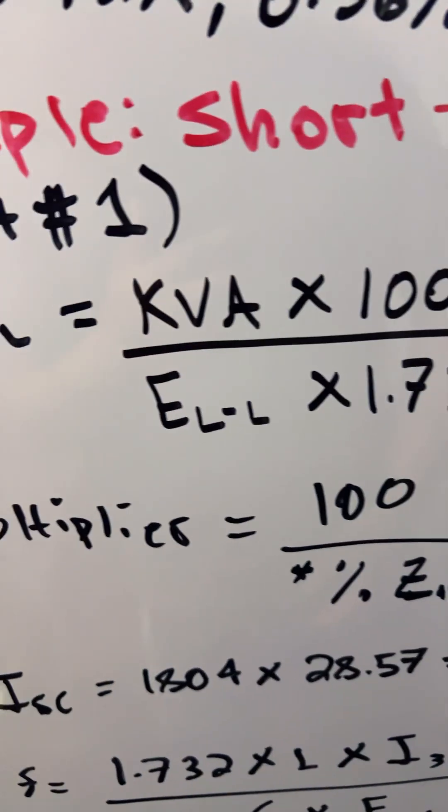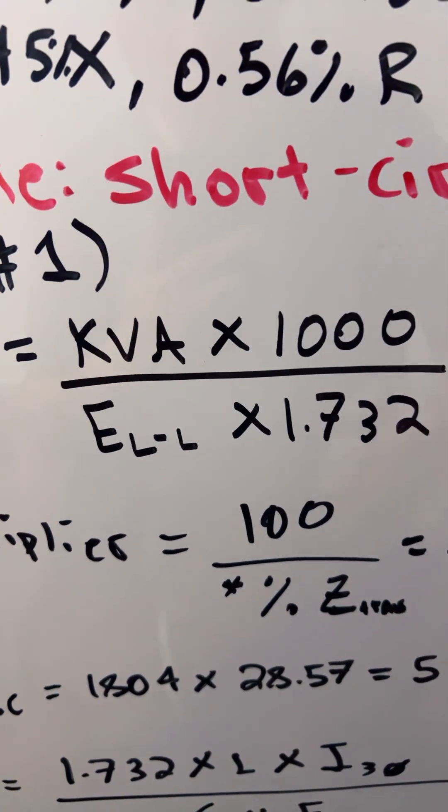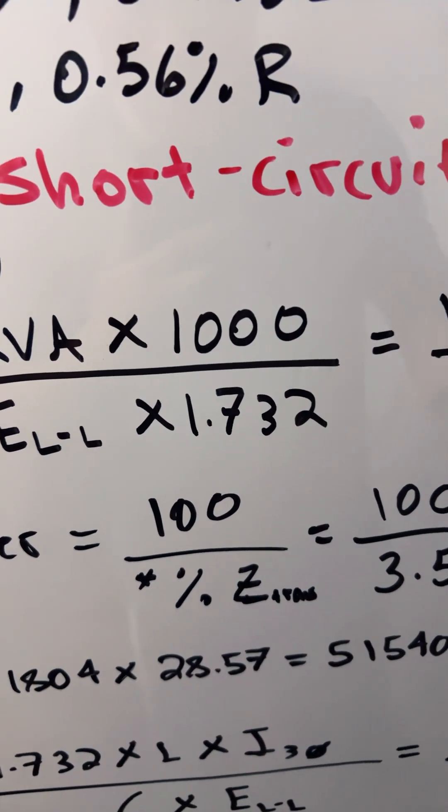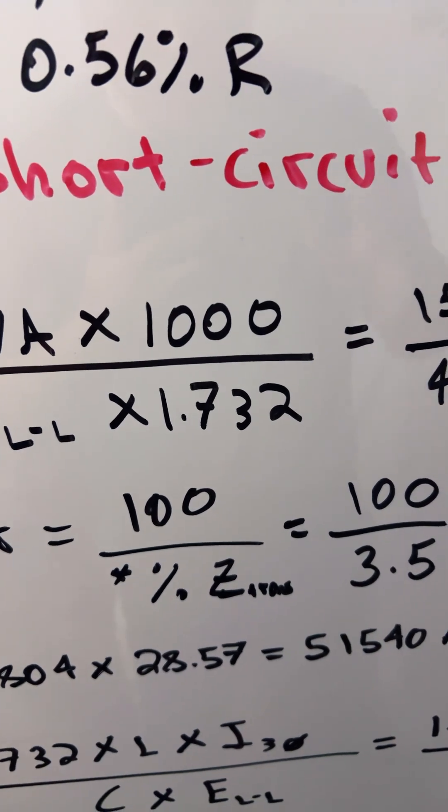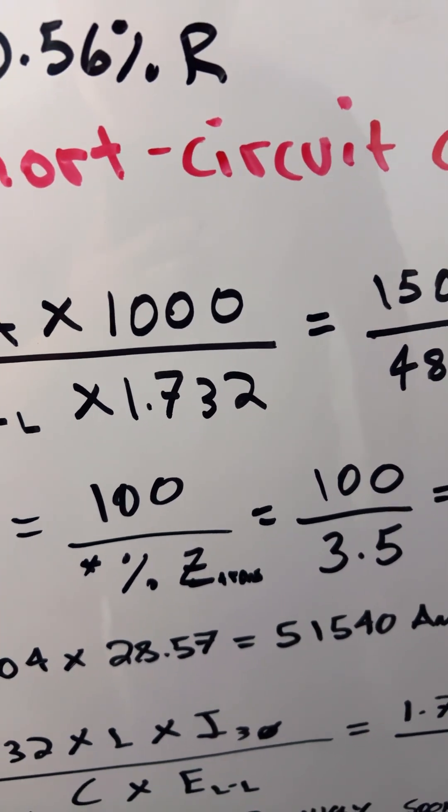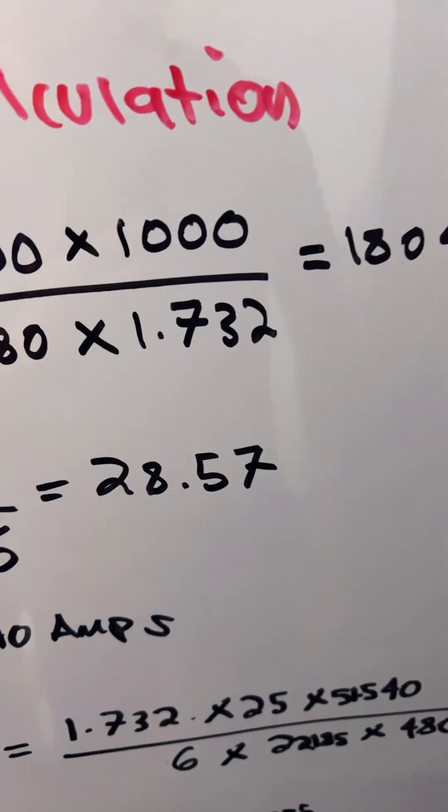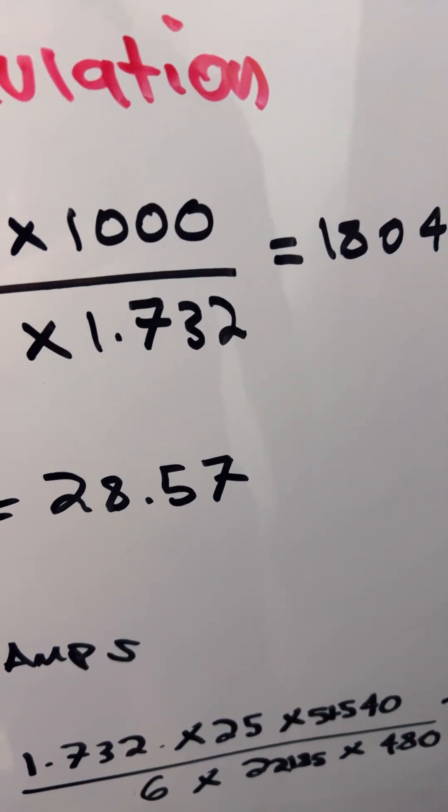Then we find the transformer multiplier. The formula is 100 over the transformer impedance, which equals 100 divided by 3.5, giving us 28.57.